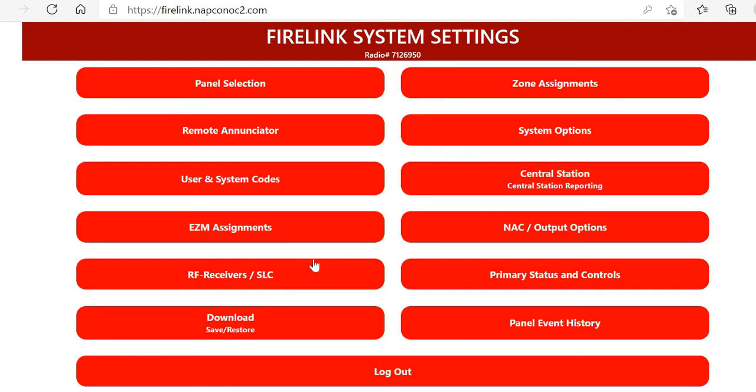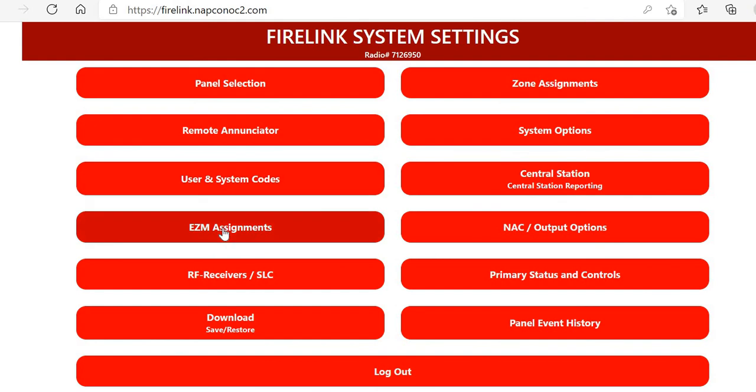The last type of zone we can add would be non-powered conventional on an EZM8. Two-wire smoke detectors are only going to work on your conventional zones one through eight on the FIM board that comes with the kit on the motherboard.